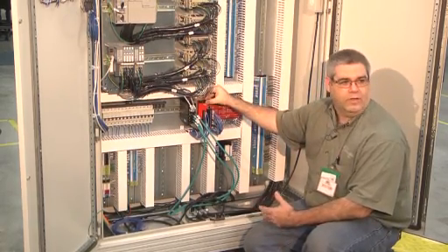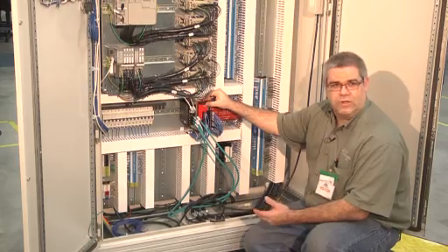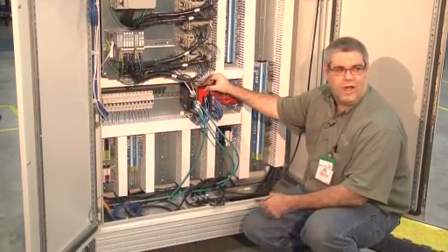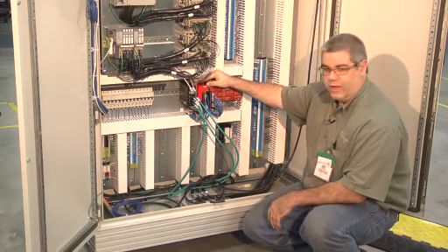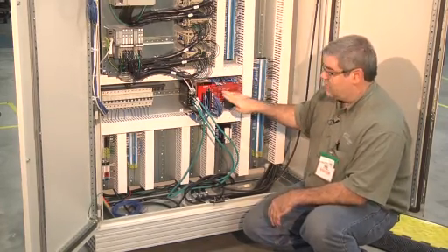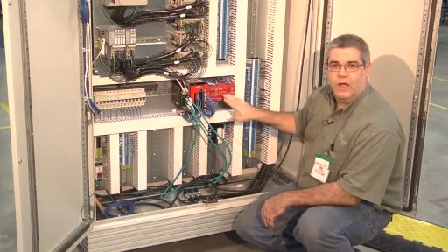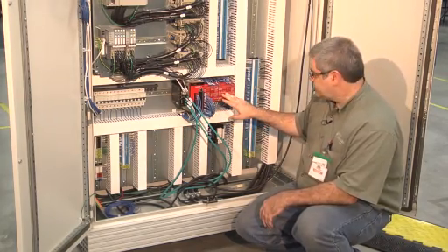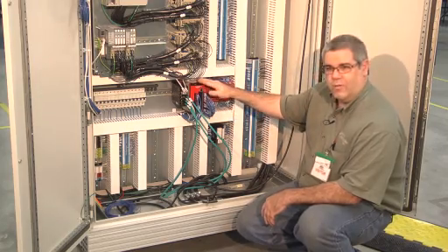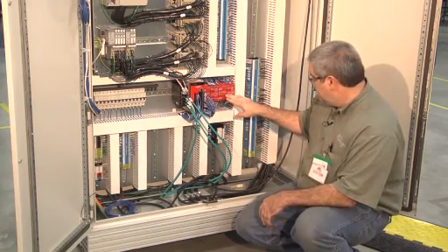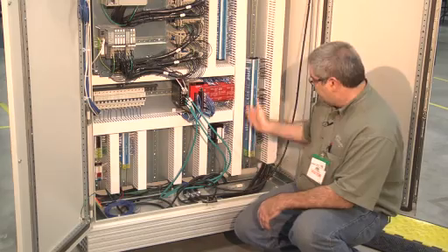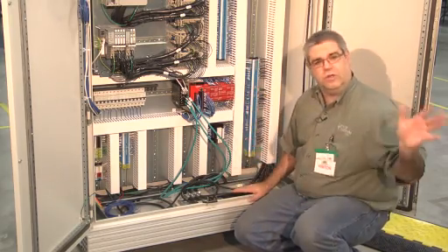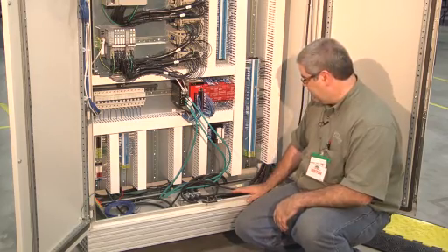It basically operates and monitors all of the safety circuits that are on board the system: light curtains, safety gates, e-stops, pull cords. They're all running through here. This then operates safety relays, a CRM relay and an output power relay for the machine. This is programmable, these are not. We have connections that go out in cables, these cables down here, that go out to the point I/O junction boxes out in the field.